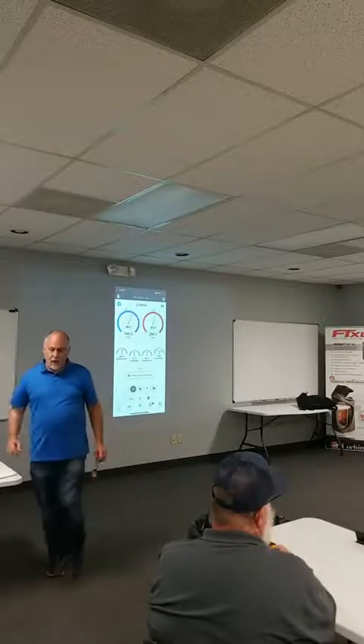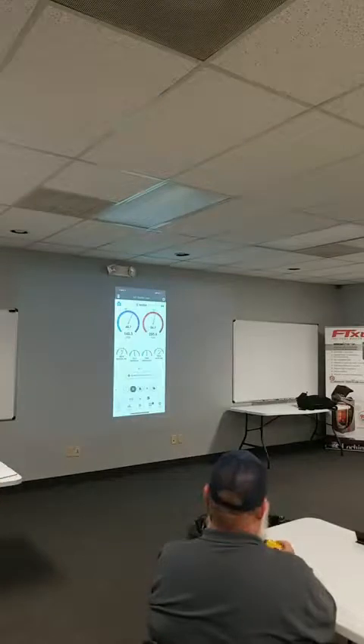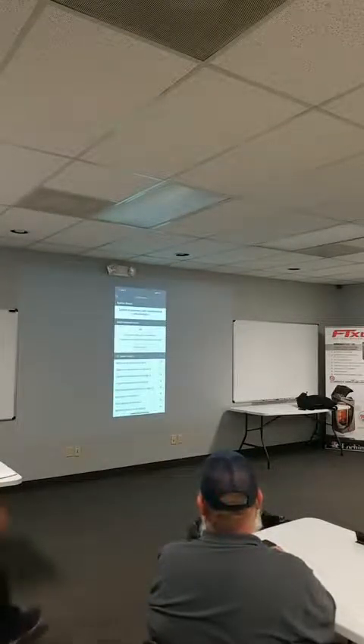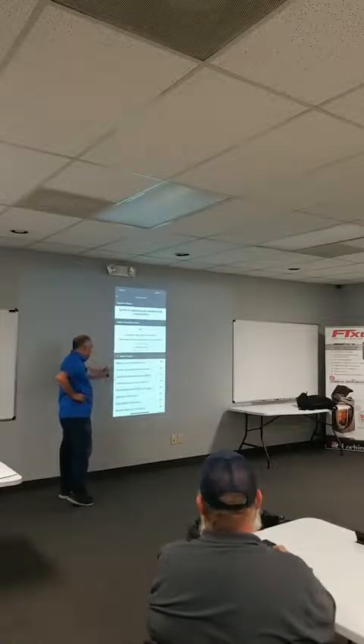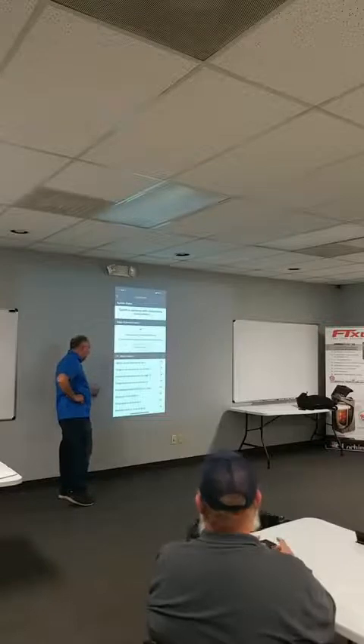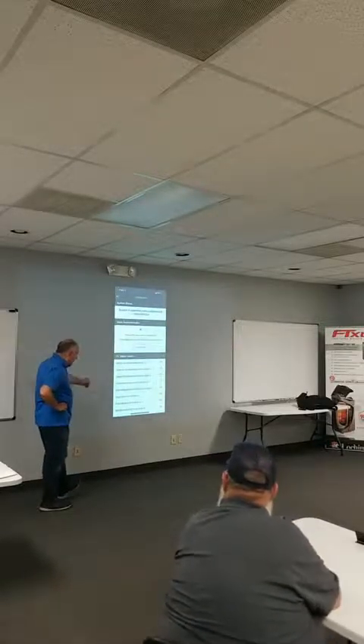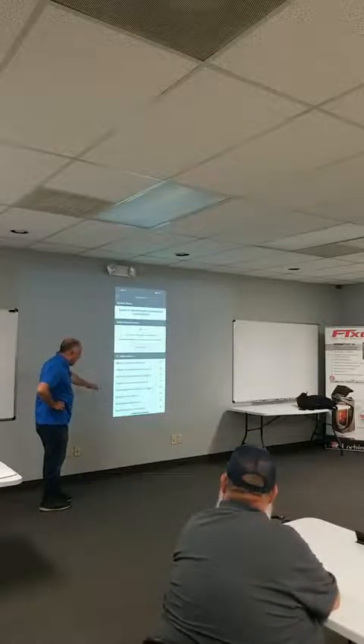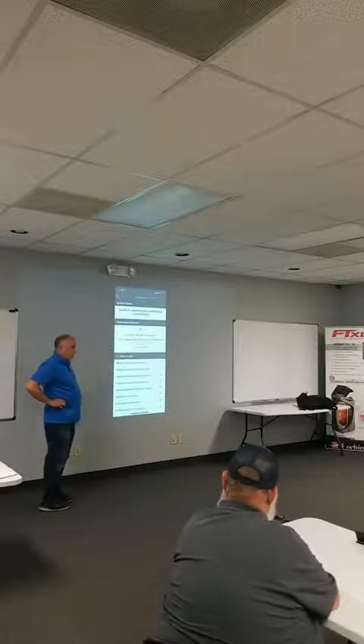So it's telling you, if you go into the minor faults, what this is telling you, if you hit this flag here, and we look at the minor faults, there still are minor faults, okay? Because the outdoor air temperature, it's picking up some things. Again, this is picking up discharge air from somewhere. Evaporator pressure is too high. Total capacity, approach is too high. There's some things here that are screwed up on this, but there's nothing in the minor faults aggregating to a major fault, right? It's just telling you these readings are a little weird on there, and it may be the best you're gonna get.